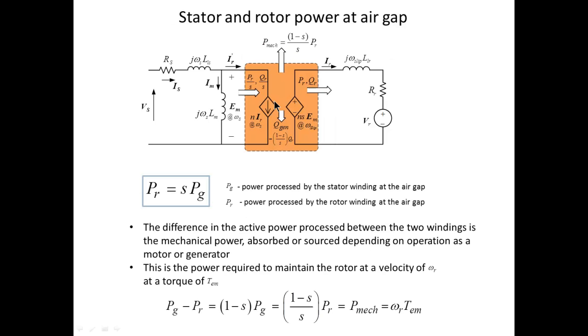If we define the power coming into the stator winding at the air gap as P_G (power at gap), then the rotor power is simply S times P_G — the 1/S relationship holds again: P_R = S × P_G. This shows that the rotor power only processes S times the actual air gap power, and S being very small results in very low ratings for the rotor side converters, and therefore the grid side converter also simply processes the power needed by the rotor side converter.